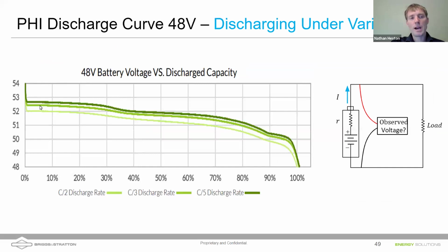If I'm discharging the battery based on state of charge, I will get a greater drop below that rate. So if I'm discharging very slowly at a C/5 rate, that means over 5 hours, and in my opinion, that would be a typical discharge rate, you will see a curve that looks like this. But if I'm discharging even faster at the same state of charge, let's go to 50%, I would see my voltage be on the order of a volt lower. If it's colder, this separation will be even more, right? So you can lose some voltage.